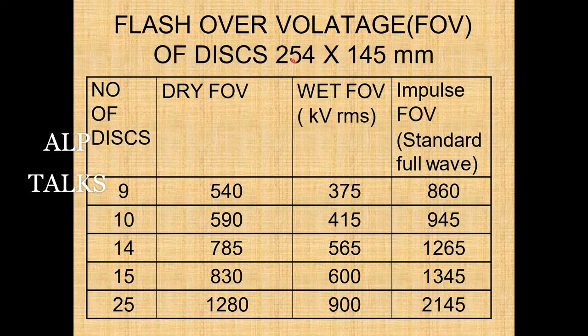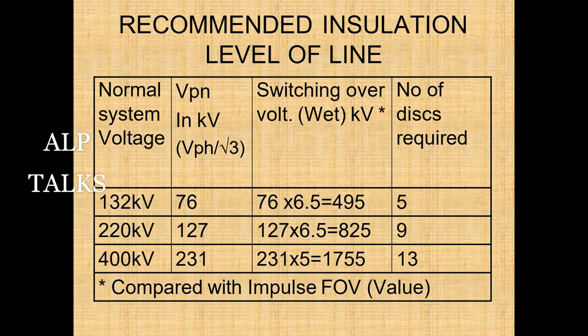For disc insulators, the number of discs varies: 9, 10, 14, 15, or 25 discs depending on voltage level. Dry FOV and wet FOV values correspond to the voltages the insulation can withstand under dry and wet conditions respectively. The standard full-wave impulse voltage is also specified — for example, for 25 discs with dry FOV of 1280 kV, the impulse FOV can be 2145 kV.